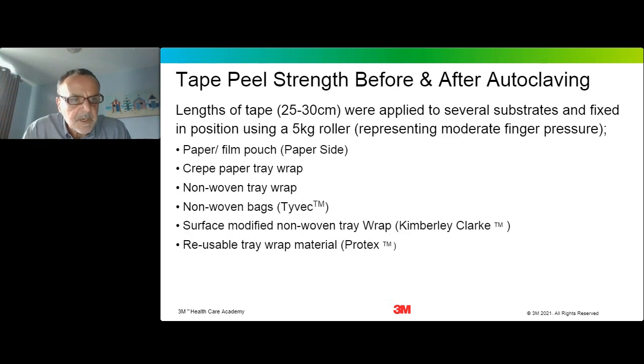So let's have a look at tape peel strength before and after autoclaving and how this would be typically tested in a laboratory situation. So in this first test, 1 foot lengths of tape were applied to one of several different wrapping materials, including the paper side of a paper film pouch, crepe tray wrap, non-woven tray wrap, non-woven Tyvek bags, surface modified non-woven tray wrap, and then a reusable tray wrap material.